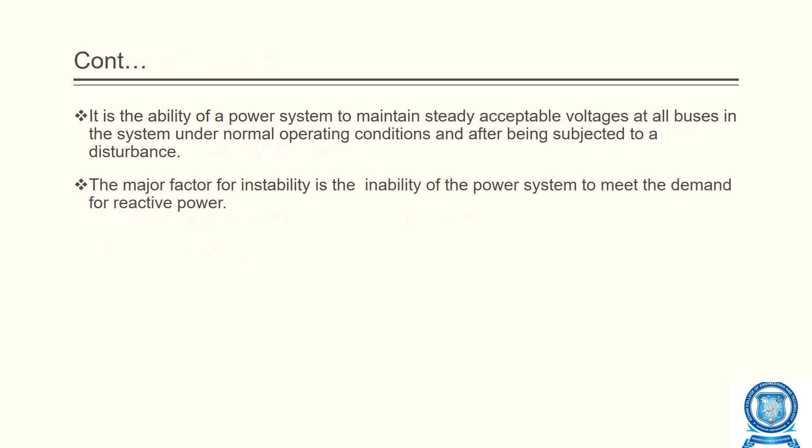Voltage stability is the ability of a power system to maintain steady, acceptable voltage at all buses in the system under normal operating conditions and after being subjected to a disturbance. The main factor for instability is the inability of the power system to meet the demand for reactive power, which is the major cause of voltage stability problems.